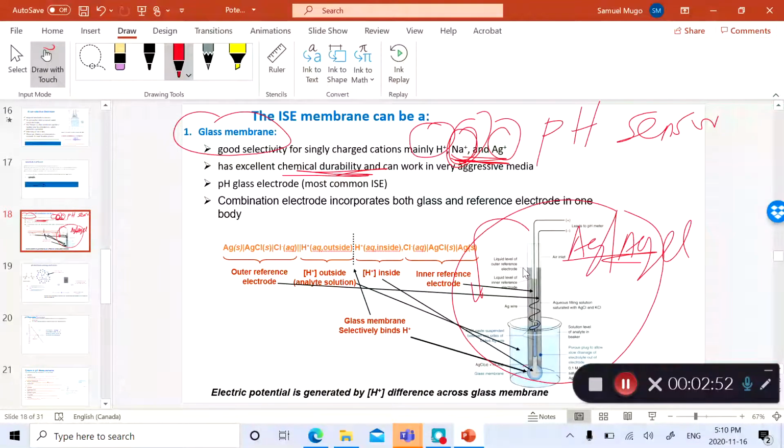And the indicator electrode, you can see, is just a glass membrane, and inside the glass membrane it has a capillary, and you fill it with a known concentration of HCl. Typically, I think it's 1 molar concentration that you fill in. And so that's what a pH electrode really is. And the glass membrane, like I've said, is selective largely to hydronium ion, and that creates what you call a charge barrier or a charge separation, giving you a voltage that you record.